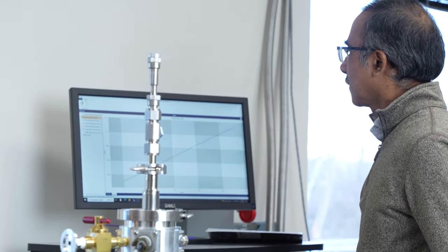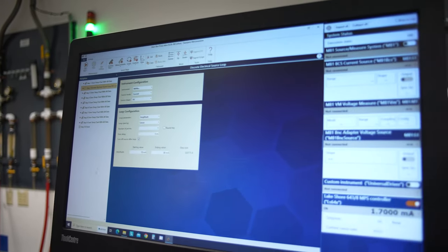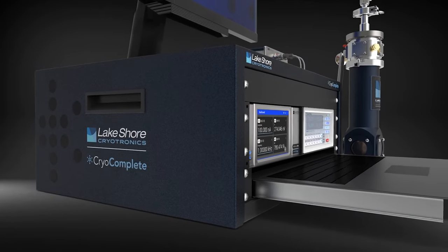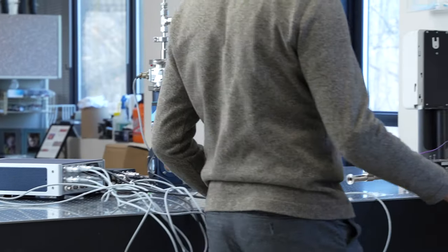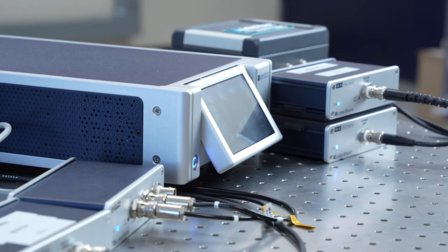The way we did this was to create a non-programming environment with drag-and-drop measurement steps that allow users to set up system sweeps like temperature sweeps, magnetic field sweeps, and sample rotation, while also controlling the measurement electronics to coordinate a full experiment. Because each part of CryoComplete — from the sensor, instrumentation, and cryostat — is designed and manufactured by Lake Shore, we have full control of optimizing the entire measurement signal path. So not only does your system setup go from months to minutes, you also have a fully optimized signal path. I can't wait to see all the research CryoComplete will enable.